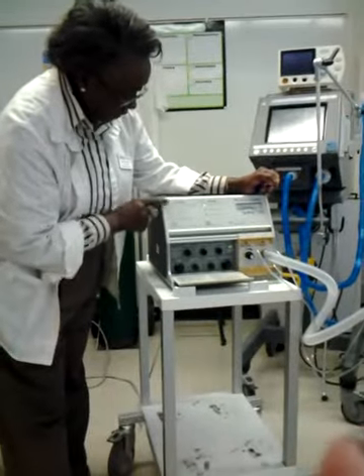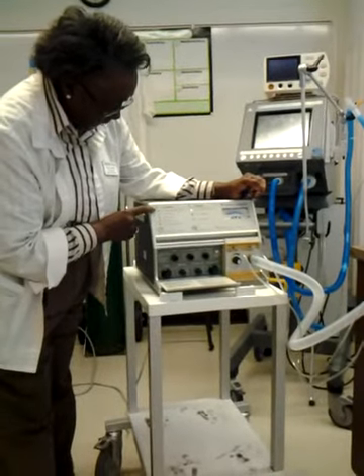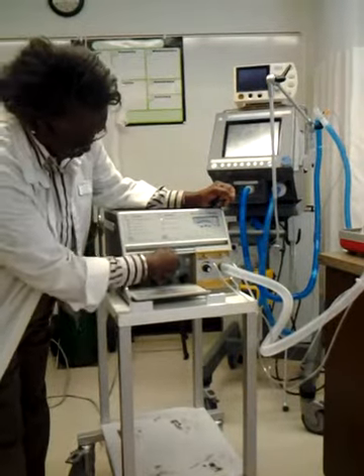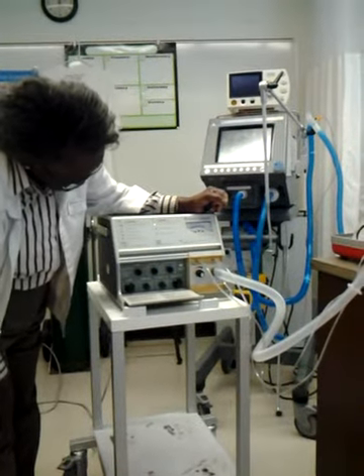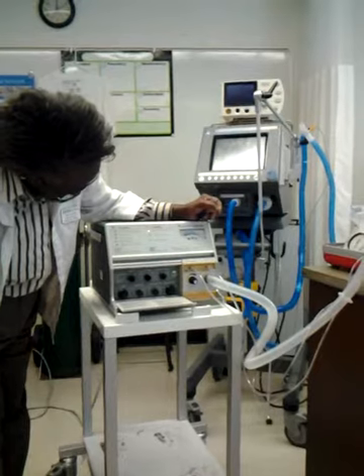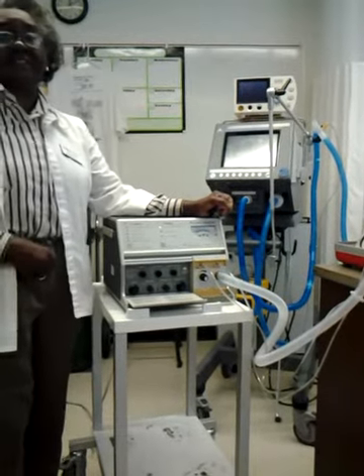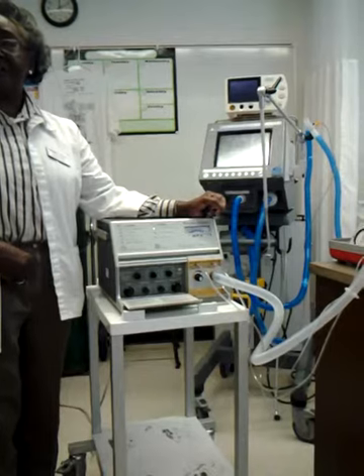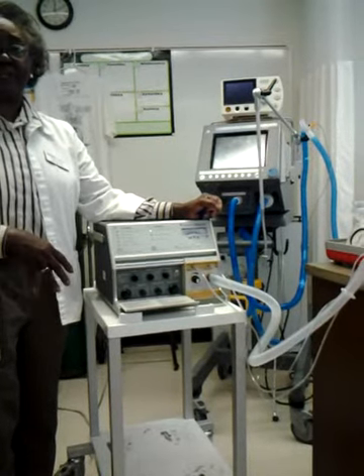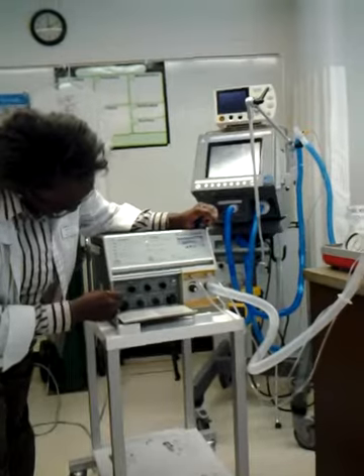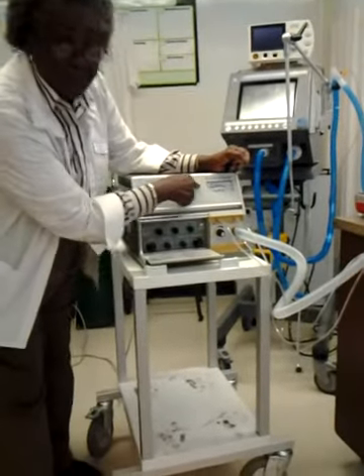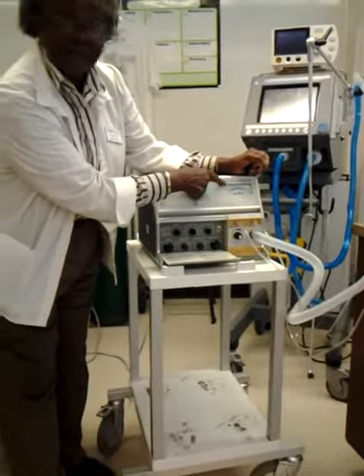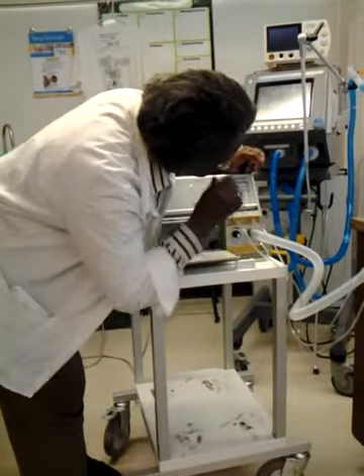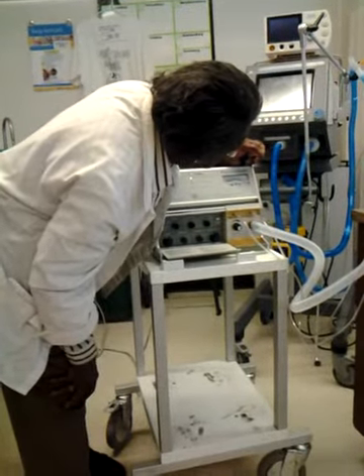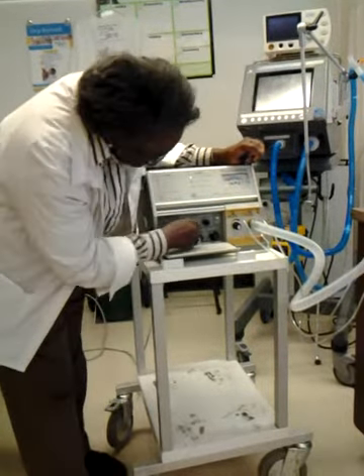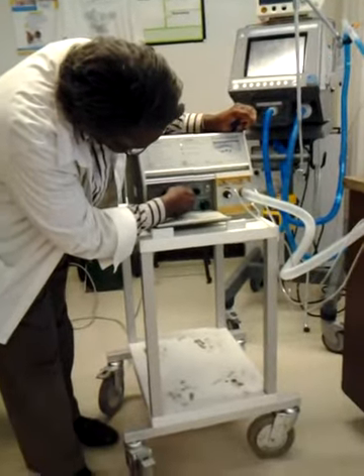Your alarms are pretty self-explanatory. For example, if I put my low pressure alarm all the way down as far as it'll go, the machine sometimes will start alarming because it's not set sufficiently. It's just trying to let you know that you don't have your alarm set sufficiently. It takes a few breaths for it to get around to doing that. So you want to set it based, like with all of your ventilators, on what your patient is doing. My peak inspiratory pressure here is about 25 centimeters of water. So I can set this up to, say, maybe about 10 or 15.